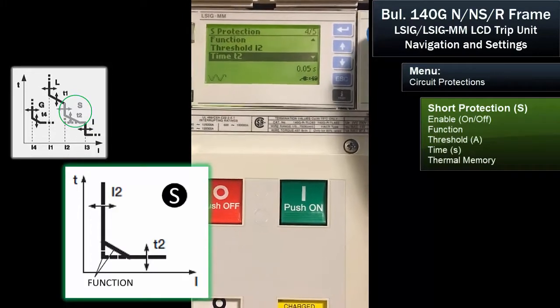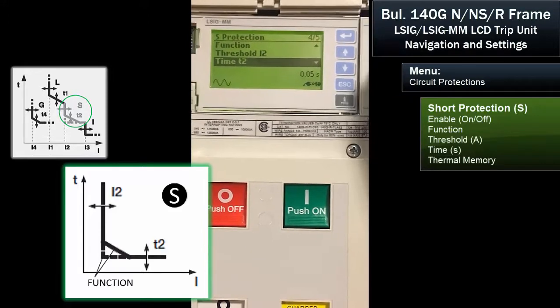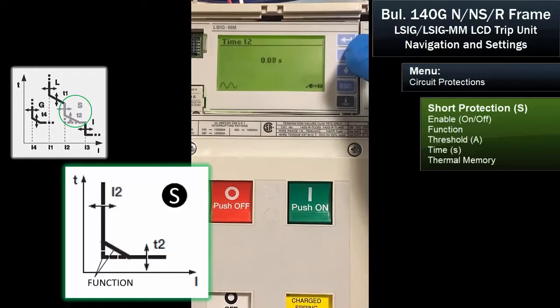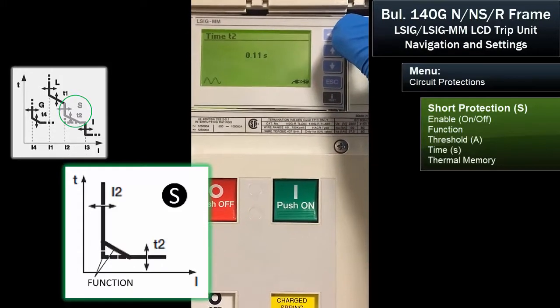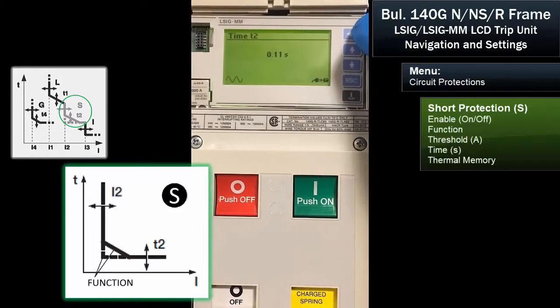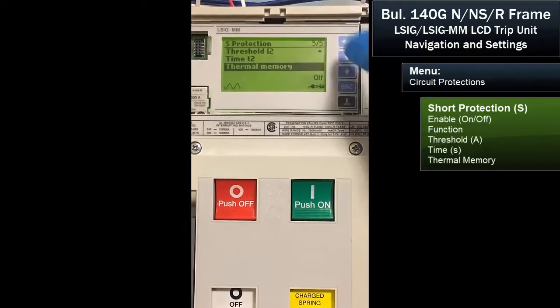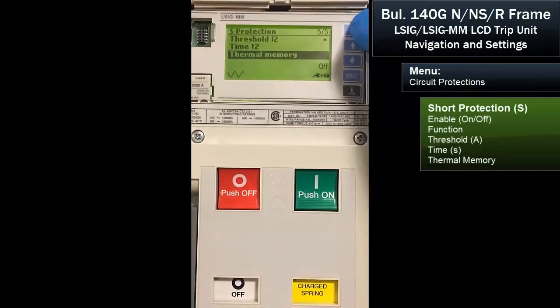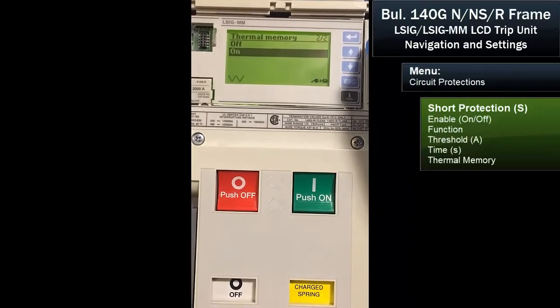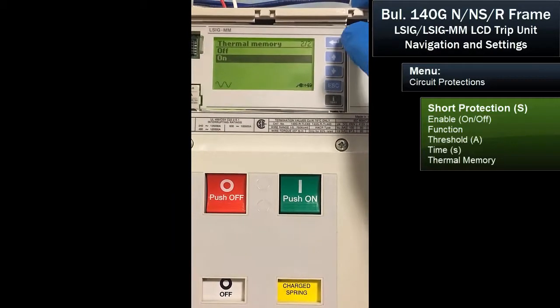Then we can set the time. T2 is actually the intersection on the curve for the short time. You can set that using your selectivity manual for how you want to have selectivity. And again, thermal memory — because we're using this to protect the wires or bus bar, we want the thermal memory on so that if we did have a trip, we have an accelerated trip time on a warm breaker.